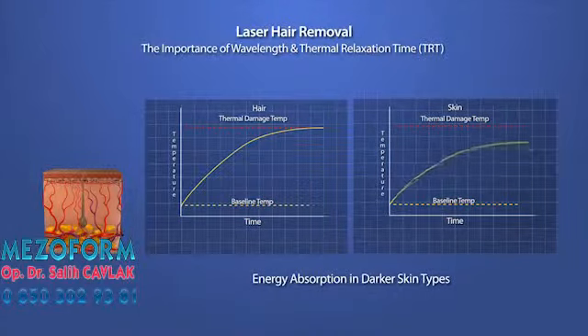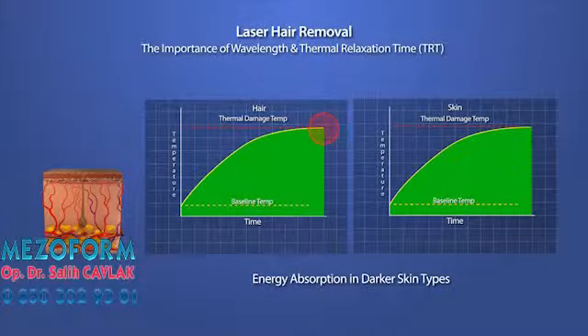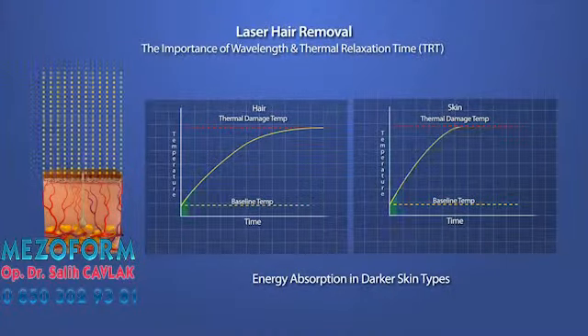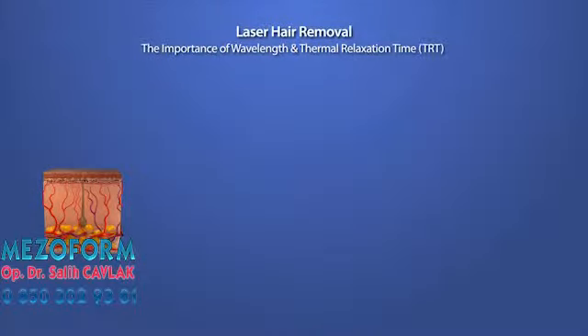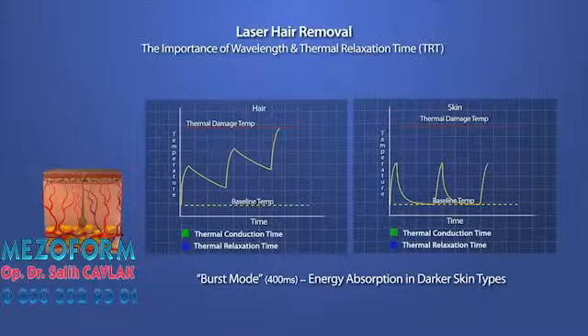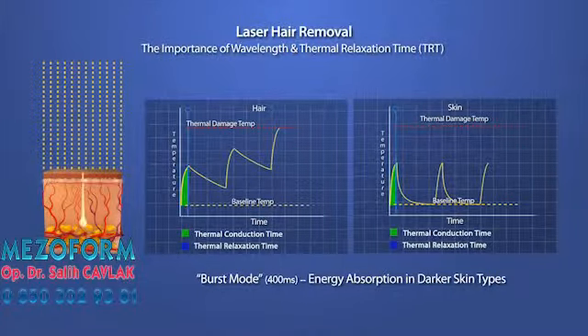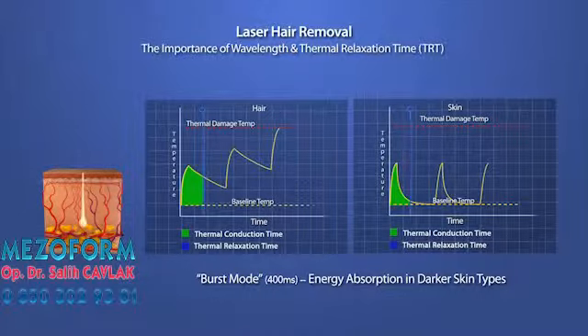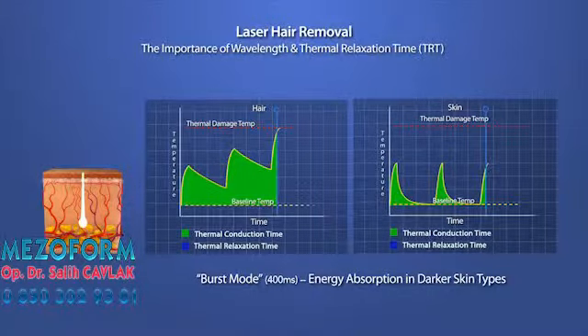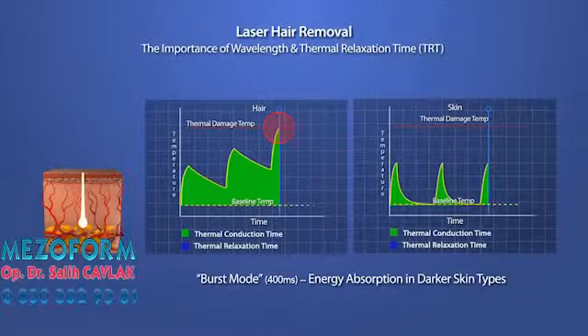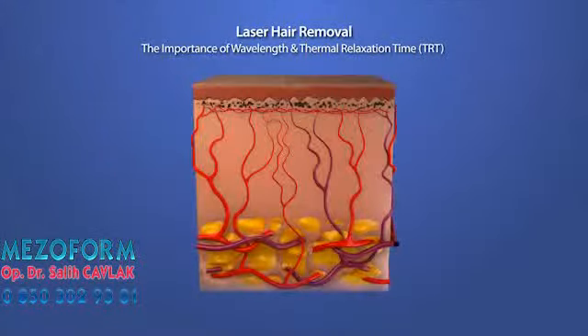For darker skin types, the melanin content increases, thus the absorption of the laser energy in the skin increases, and temperatures can reach critical levels before the hair is damaged. For these darker skin types, a pulsing technique, burst mode, is utilized where the laser produces the energy in bursts. Though there is higher absorption of the laser energy in the skin due to its melanin content, it is allowed to cool between pulses, and since the thermal relaxation time of the hair is longer than that of the skin, the hair retains most of the heat. As subsequent pulses are delivered, the hair temperature builds higher, but as before, the skin is allowed to cool, and ultimately a pulse is delivered where a hair kill temperature is achieved, but the skin remains undamaged.